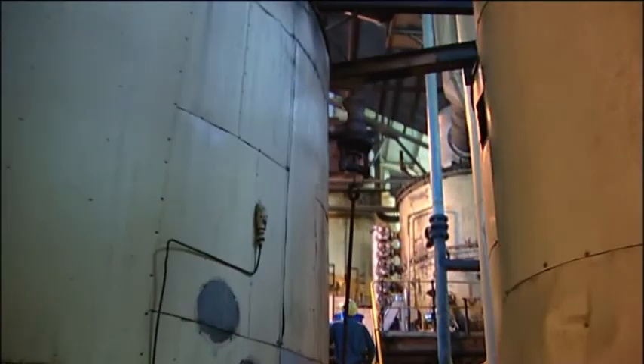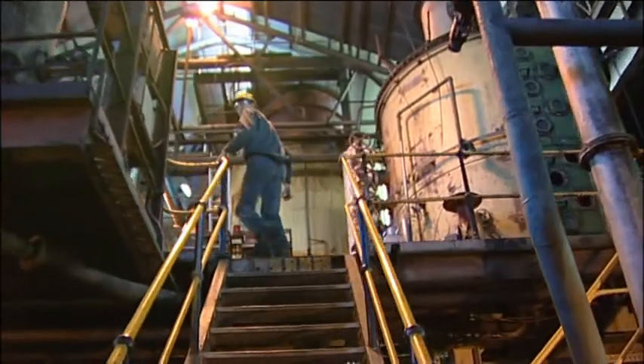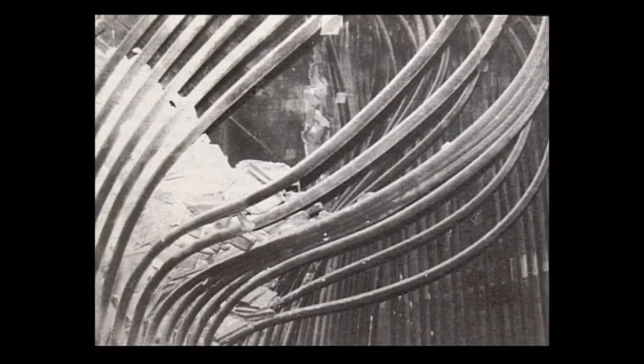One of the worst things that happened, on the 1st of September 1981 at 3 o'clock in the morning, was the single boiler that we have virtually had a meltdown of the furnace. The water ran low in the boiler. A tube blew out at the bottom of the furnace, and the fire kept on going, and it's over 1,000 degrees Celsius in the furnace, and all the internals, all the tubes, just collapsed inwards. With one single boiler, it looked like we wouldn't crush for the remainder of the year.